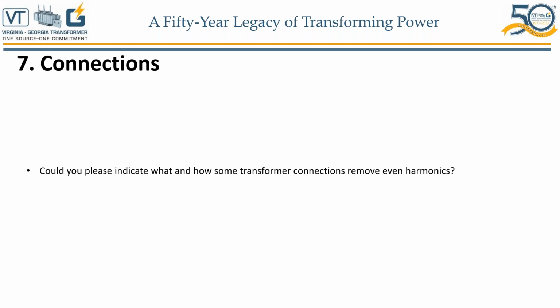or even lead to tank clearances. And then we also end up lowering the flux density, kind of connected to that 10% overvoltage thing, because when the harmonics are too much, the voltage of the transformer will act as if it's increasing. To overcome that, we decrease the flux density to allow the transformer to operate without any issues at higher voltages. But like I said, please email me. We have a full-blown presentation on harmonics, and I'll be happy to email you that presentation.